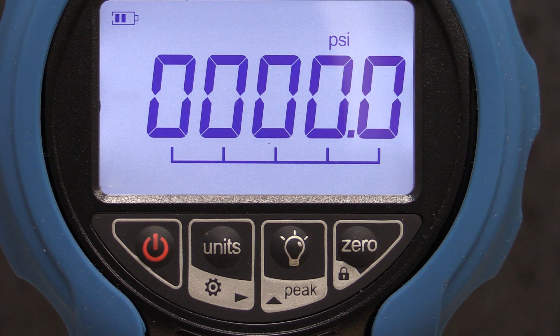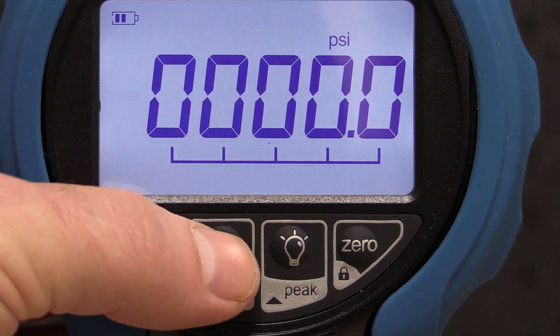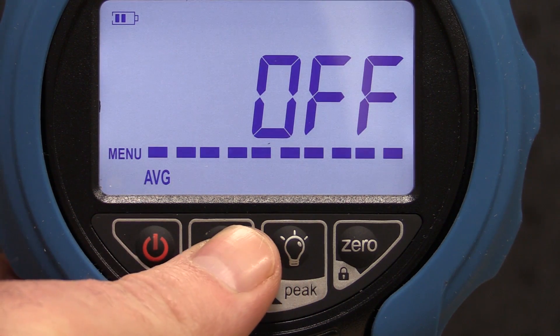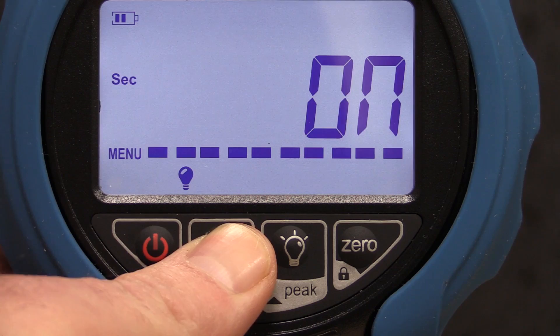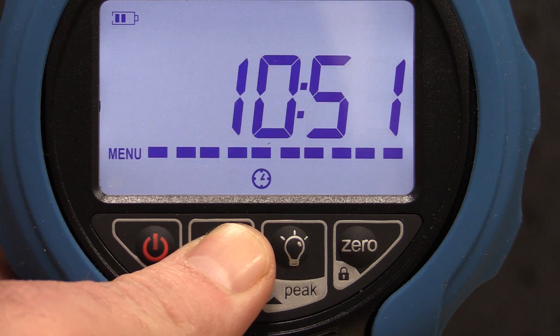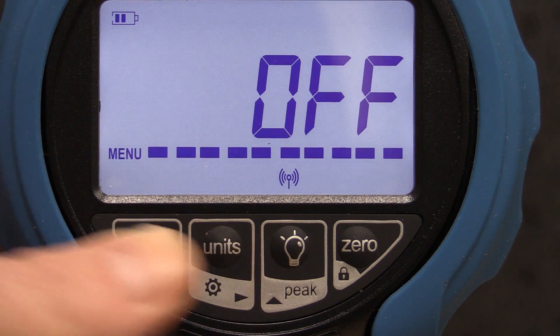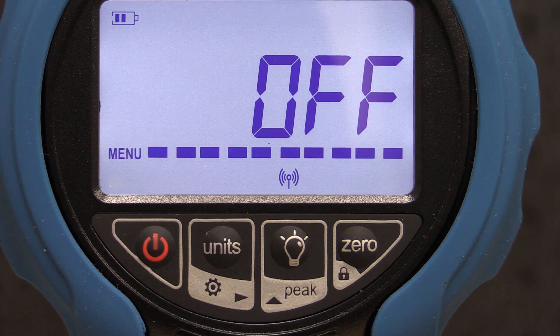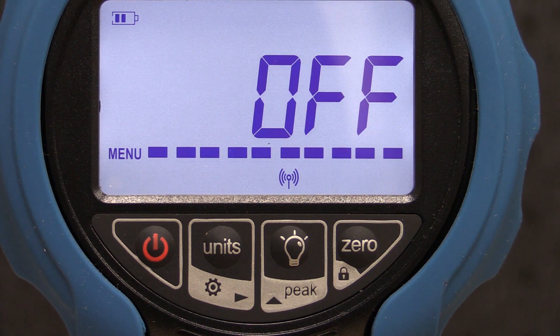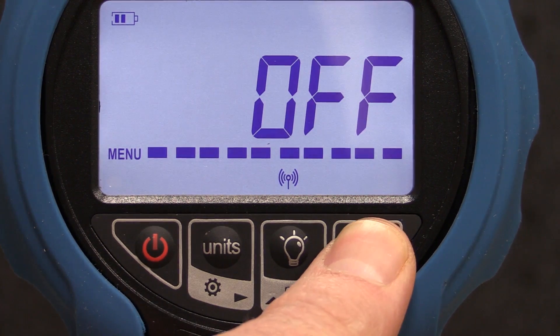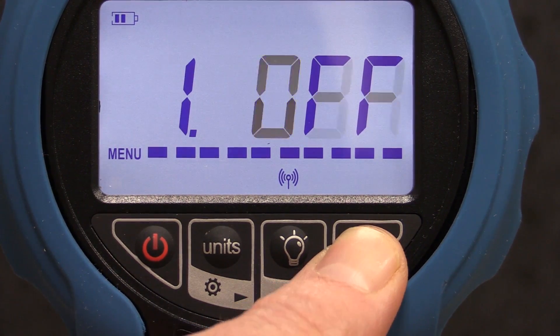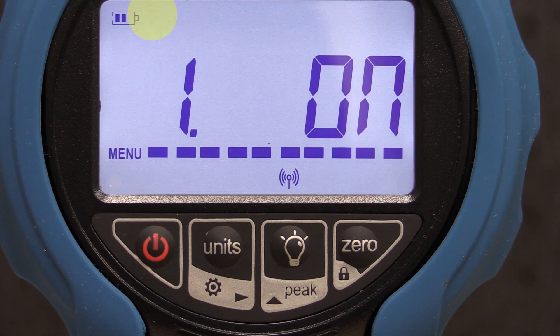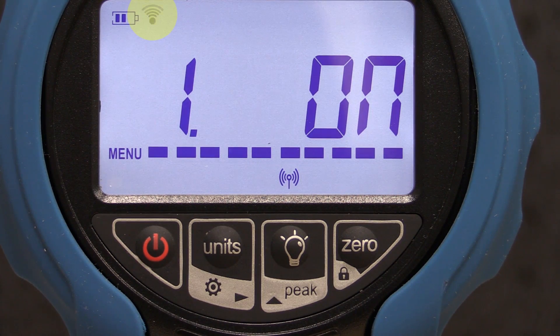To enable the wireless on the ADT-680W, press and hold the Units key to access the main menu. Press the Units key again to navigate to the right until you see the wireless icon. Press zero to enter the wireless menu. You will now see off if the wireless is disabled. To enable the wireless, press zero and you will see the menu indicate on and the wireless icon will flash at the top left of the display.